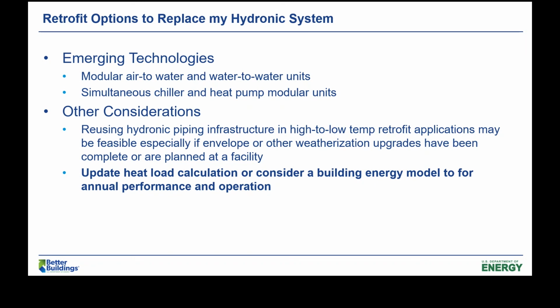If I don't need that capacity, it changes the options on the table. Not only can I buy a smaller piece of primary equipment, but if my old system was on the higher temperature range - where heat pumps aren't always able to generate 180 degree Fahrenheit water - and if my heat load has come down enough that I can meet today's heating load even using the same piping infrastructure at a lower temperature, then my pathway to decarbonizing has more options. So really looking at that heating load and for opportunities to get to a lower temperature system - both of those are critical in transitioning to heat pumps in the future.